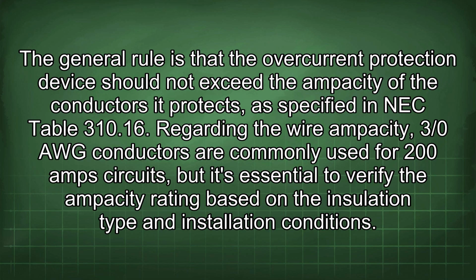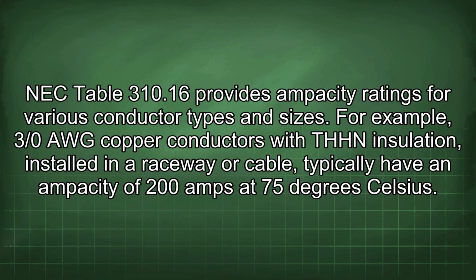Regarding the wire ampacity, 3/0 AWG conductors are commonly used for 200 amp circuits, but it's essential to verify the ampacity rating based on the insulation type and installation conditions. NEC Table 310.16 provides ampacity ratings for various conductor types and sizes. For example, 3/0 AWG copper conductors with THHN insulation installed in a raceway or cable typically have an ampacity of 200 amps at 75 degrees Celsius.